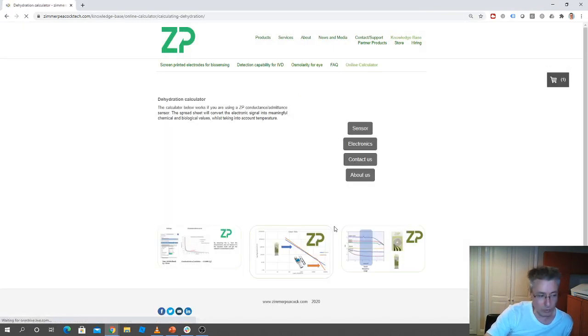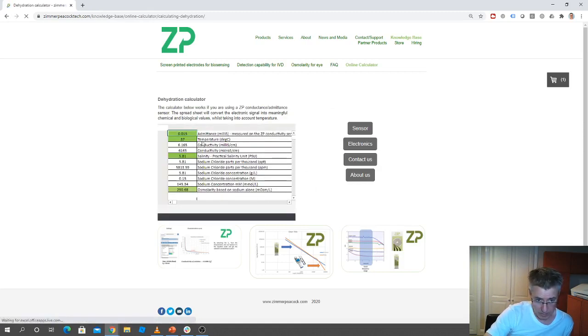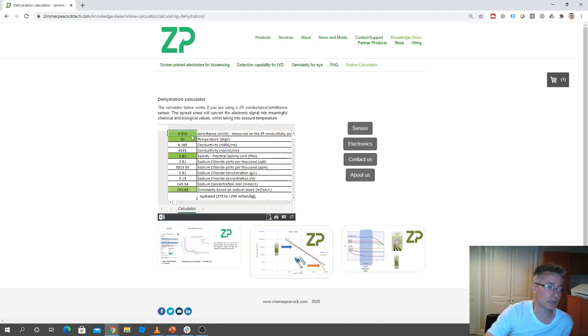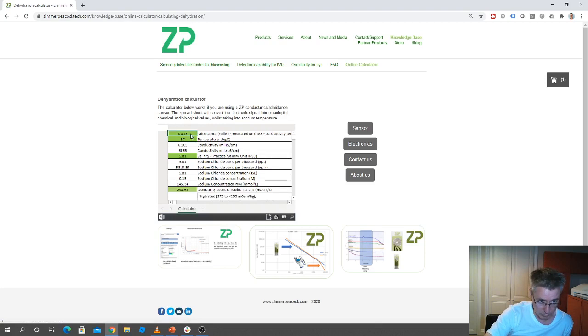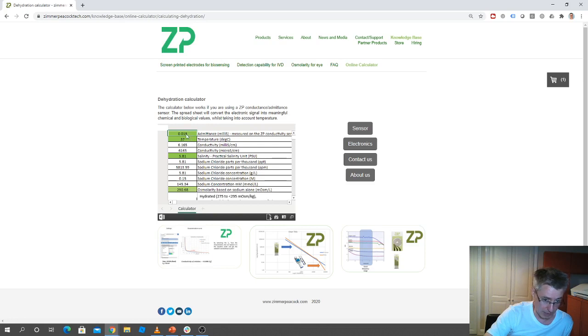So when you're working in the R&D setting, you'll be recording values, but you need to understand what those values are in terms of osmolarity. So for example, here I've recorded an admittance in millisiemens of 0.015, and that translates to about 290 in terms of osmolarity.